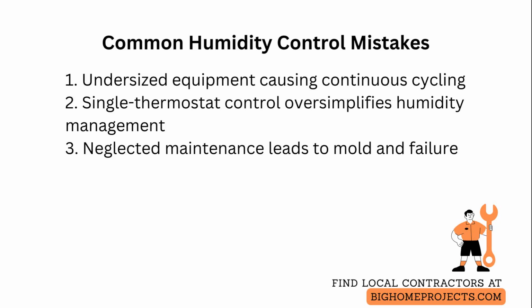Common mistakes include undersizing equipment, which causes continuous cycling and inadequate moisture control. The fix is to calculate latent and sensible loads using expected occupancy and local climate data, then choose a unit with some capacity margin. Oversimplifying control logic by relying solely on a single thermostat often results in rooms that are too dry or too humid. Resolve this by using dedicated humidistats or multi-sensor setups, and by integrating humidity schedules into your control system. Neglecting maintenance leads to mold and system failure. Set calendar reminders for cleaning, replace consumable parts on the manufacturer's timeline, and confirm condensate drainage and antimicrobial components are functioning.